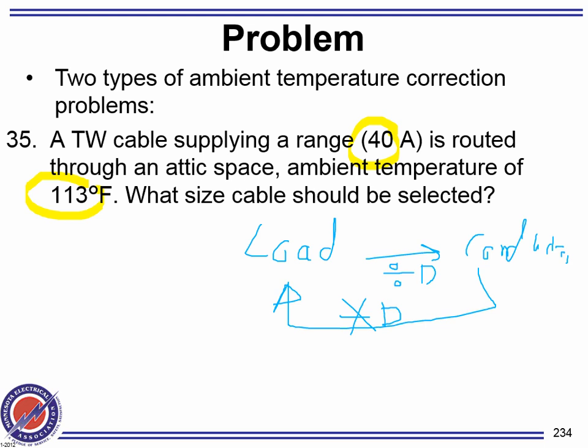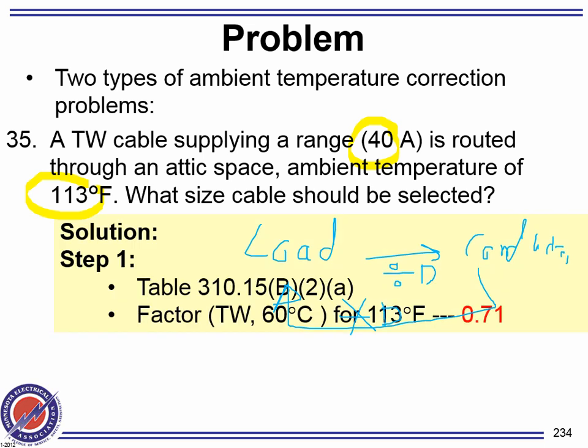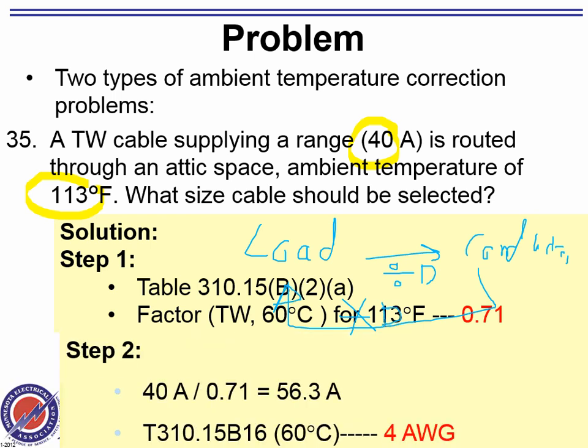Okay, so TW, where are you guys going to go? What's the derating factor for TW? Under the 60-degree column. Why do you go to the 60-degree column? TW, you have no choice. So your derating factor is 0.71. Gentlemen, then you take 40, divide it by 0.71, you end up with 56.3.